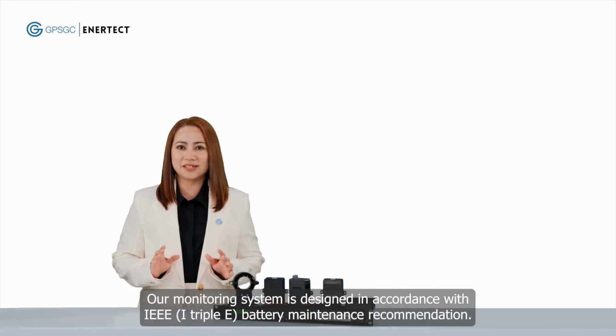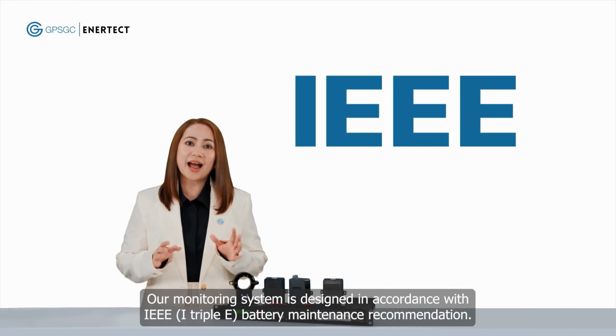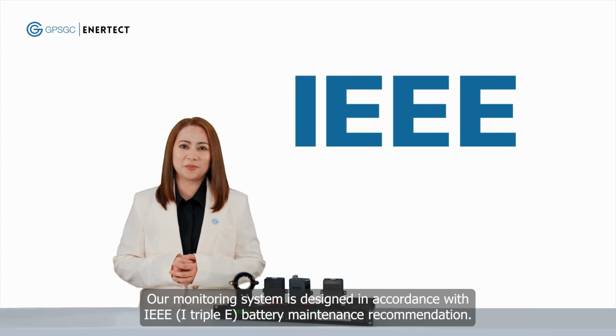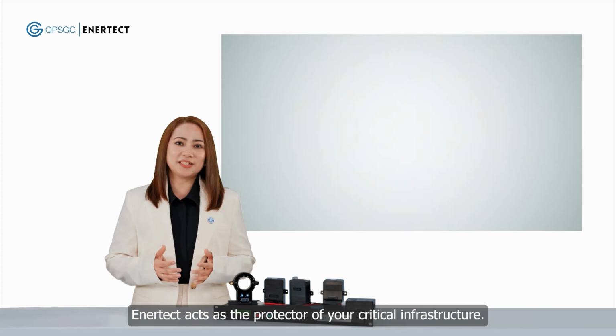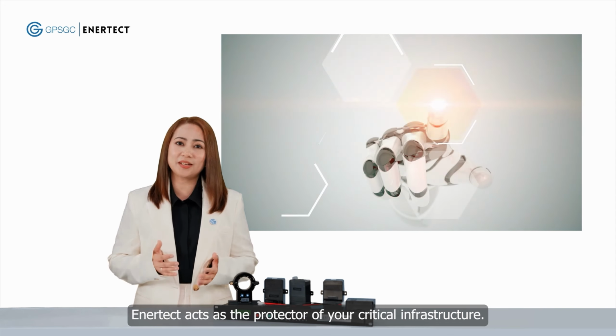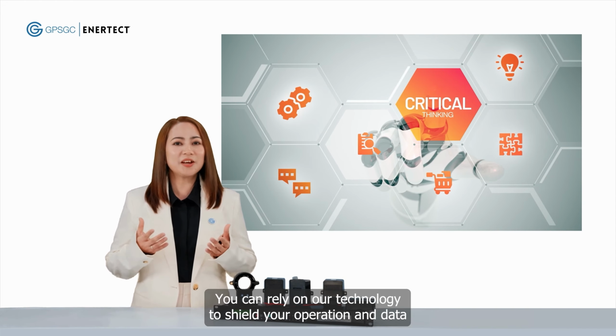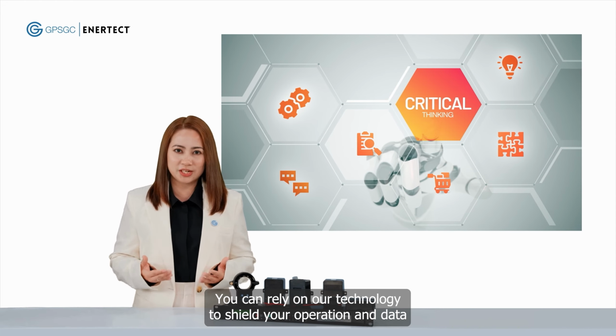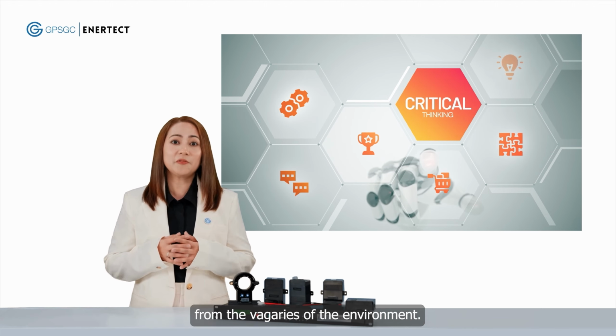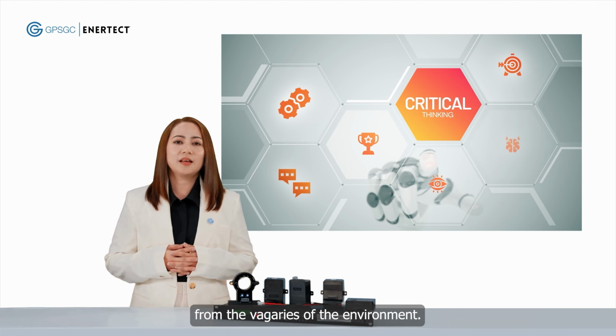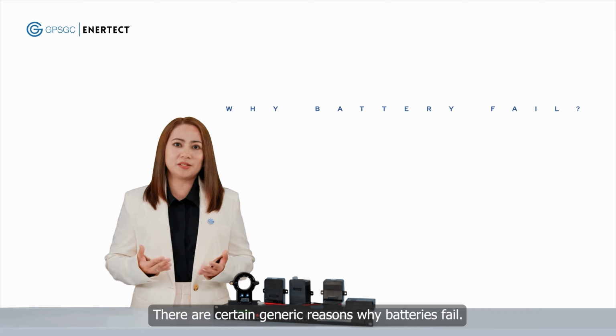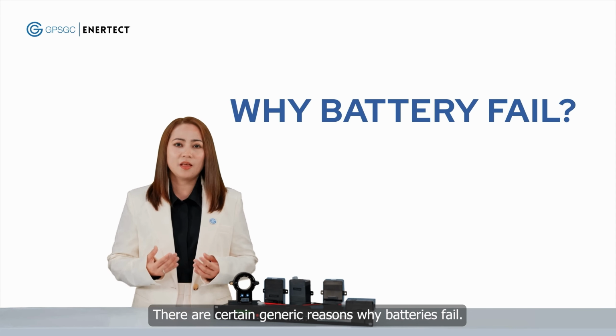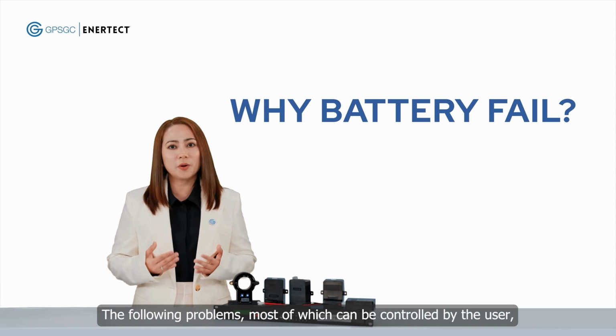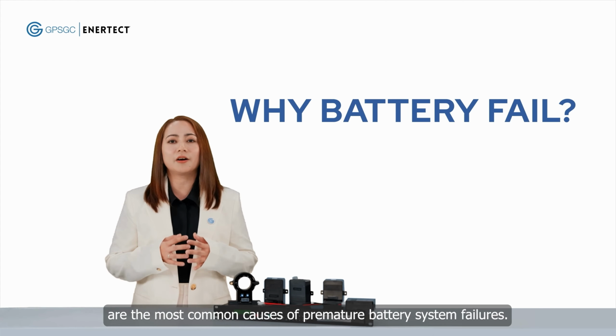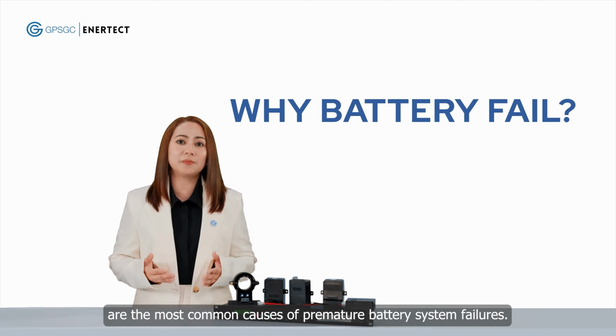Our monitoring system is designed in accordance with IEEE battery maintenance recommendation. ENERTECT acts as a protector of your critical infrastructure. You can rely on our technology to shield your operation and data from the vagaries of the environment. There are certain generic reasons why batteries fail. The following problems, most of which can be controlled by the user, are the most common causes of premature battery system failures.